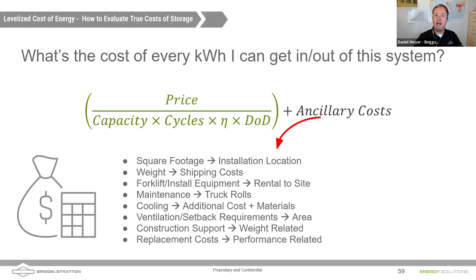15-year warranty on the 6.6, unlimited cycles at 100% depth of discharge. We expect around 6,000 cycles if you're charging at a C/2 rate -- divide 6,000 by 365, that's about 16 years. If you're hammering on the batteries, more like 4,500 cycles. In our lead acid battery days, depth of discharge always determined the life of a battery. That's still somewhat true for these lithium-ion chemistries, but more so it's the rate at which you're charging and discharging. Most people aren't going to be doing an hour-and-15-minute rate like this example. Usually you charge the batteries over the course of a day when the sun's up, and discharge them over the course of the night. Still using lithium iron phosphate.